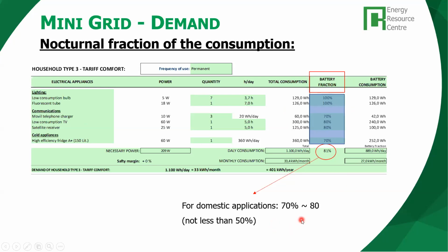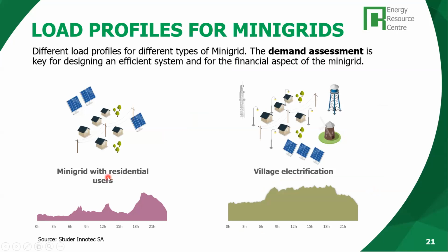For domestic applications, typically 70 to 80% night fraction is what we find, okay, because there's a lot of lighting consumption activity in the houses. Household use is normally in the evening or at night, okay? So high levels of battery fraction are normally expected in mini grids where there's a lot of residential consumption. In any case, not less than 50%. That, of course, depends on each community. Again, if you remember the presentation from engineer Pablo from Studer, he was telling us about the difference between a mini grid with only residential users, with, again, a peak in the evening for the consumption, or a mini grid where there are different productive uses and businesses, where the load curve doesn't have these huge peaks in the evening, but higher levels of consumption for the whole day.